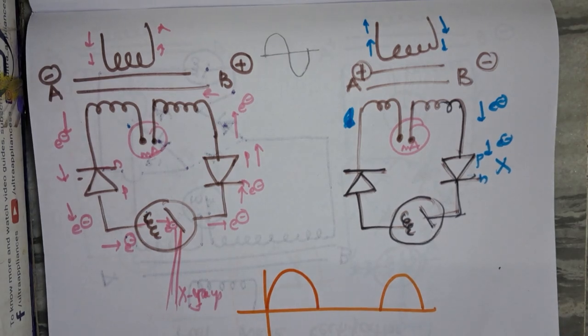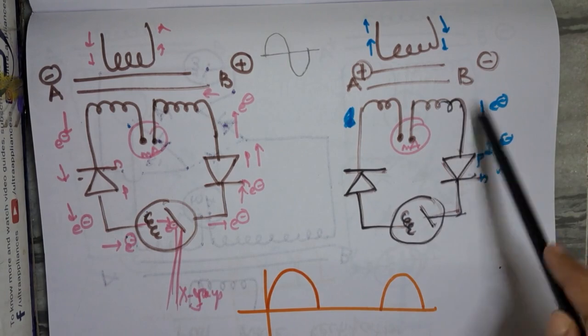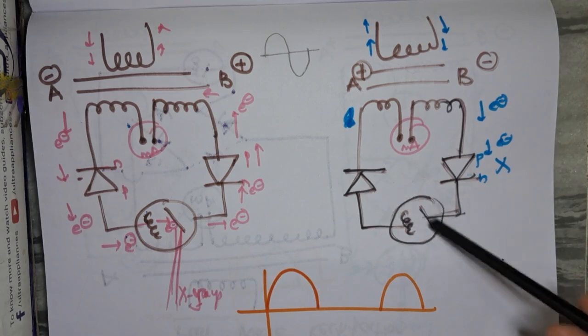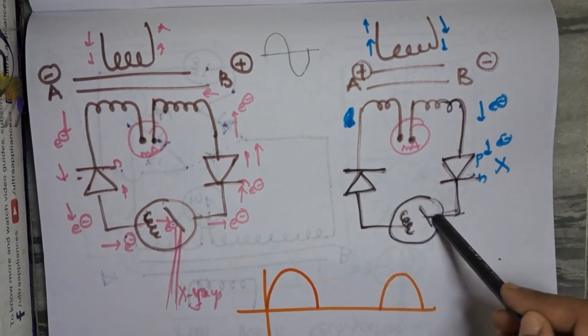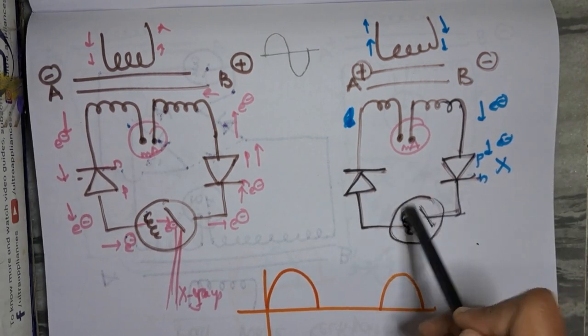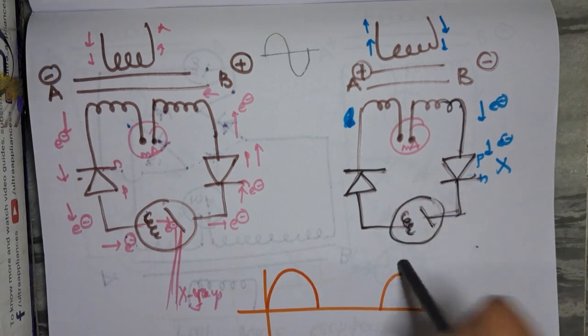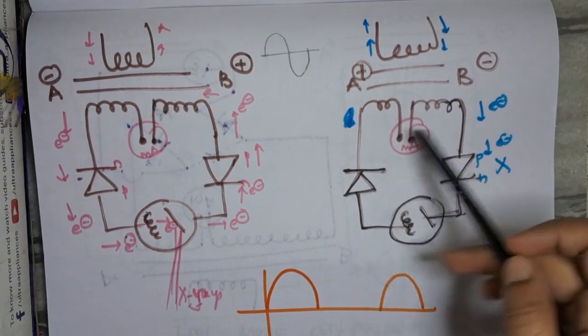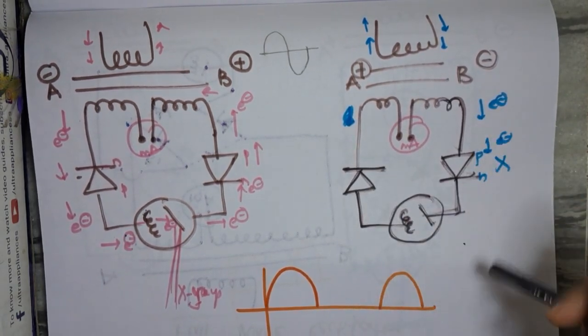Previously, when you have seen the usage of X-rays without a rectifier, in such cases the electrons will reach this anode, and the anode gets heated, and as a result the electrons from the anode will accelerate and bombard the filament and damage it. This problem has been corrected with the use of two silicon rectifiers.